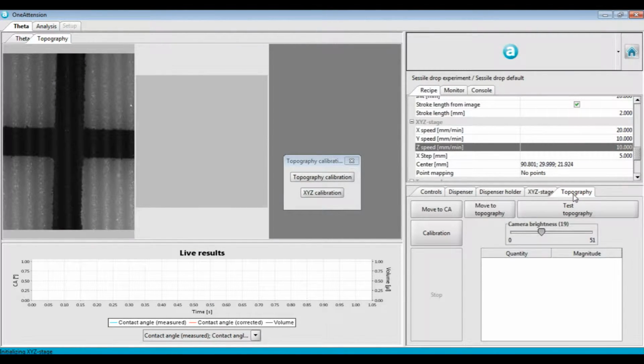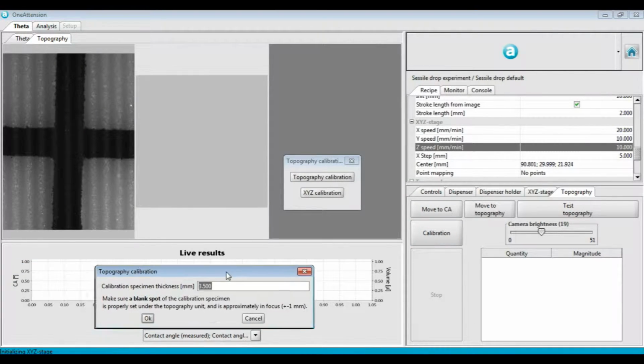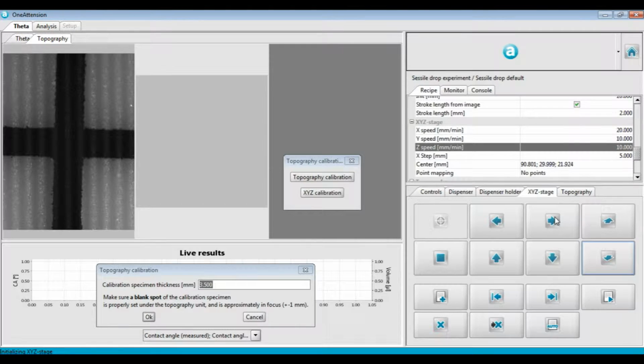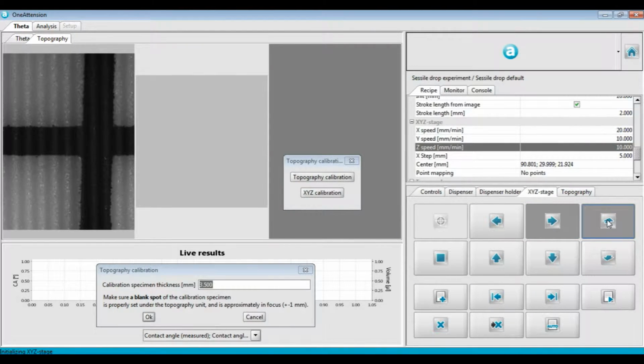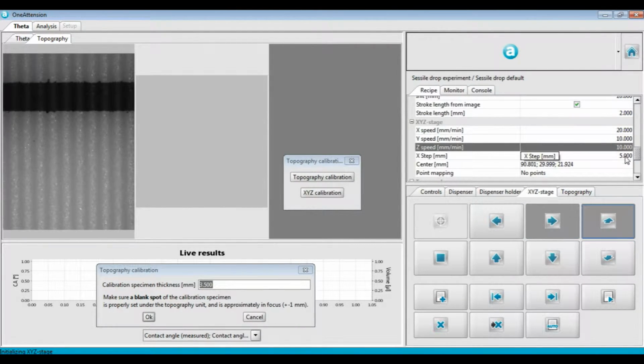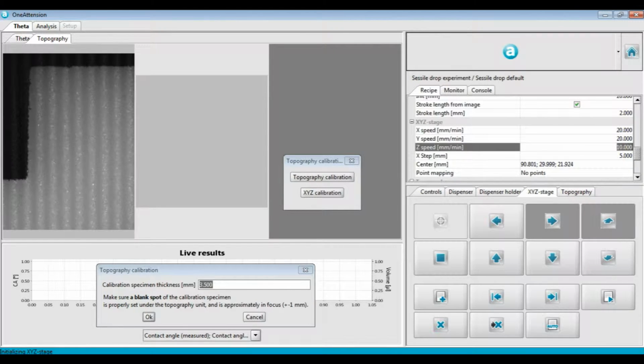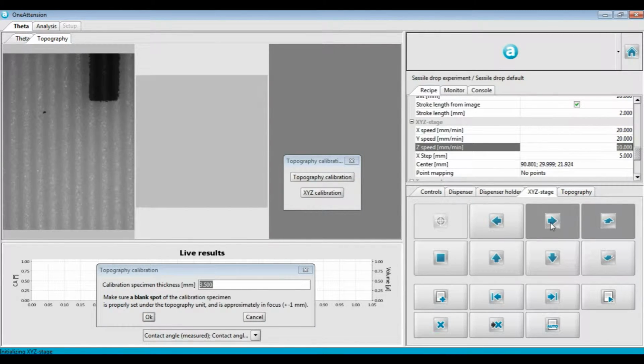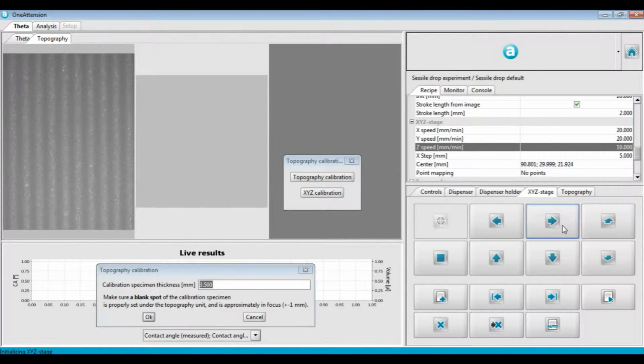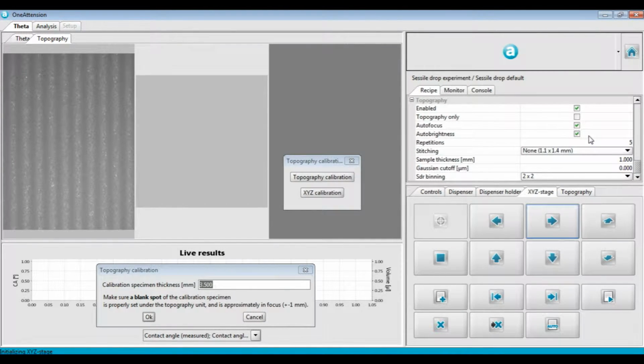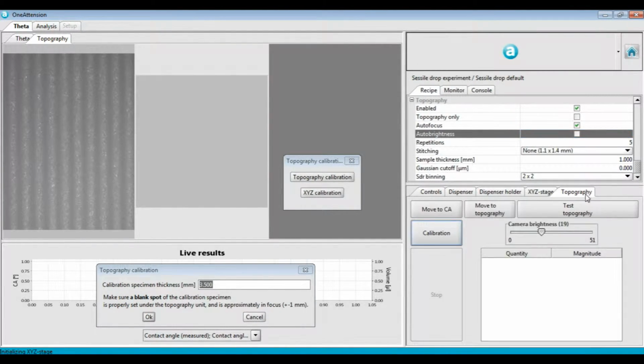Now we go back to the Topography tab in the bottom right, bring up the calibration, and now we're going to switch to the Topography calibration. Once again, instructions pop up telling you what to do, but basically we need to move to an area of the sample which is completely white, without any hash marks present. Leave the value in the field at its default value, and once we've reached a pretty good area without any noticeable defects, we can hit OK.